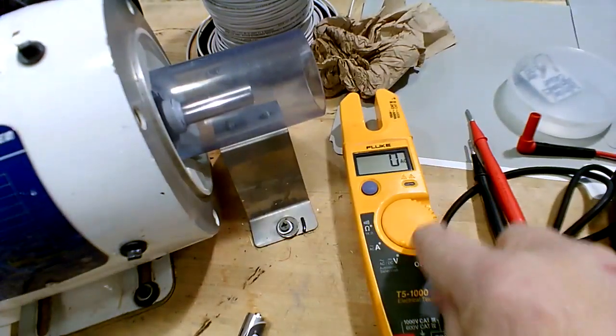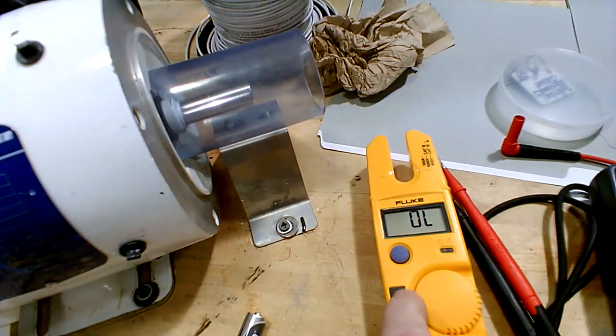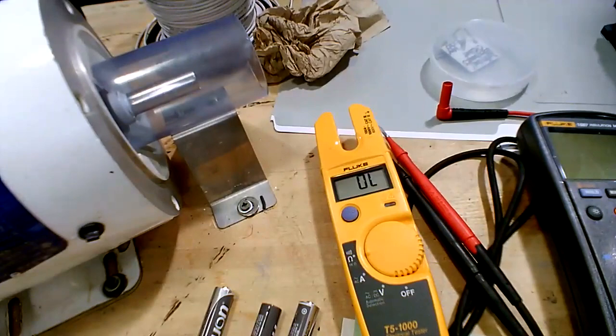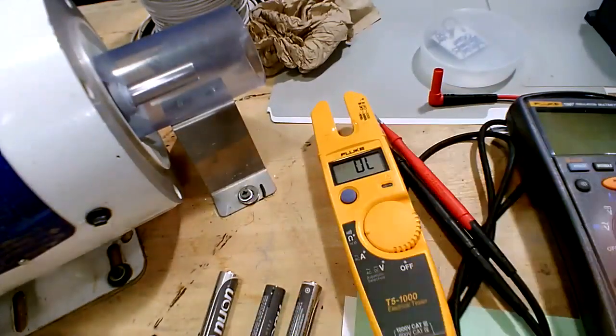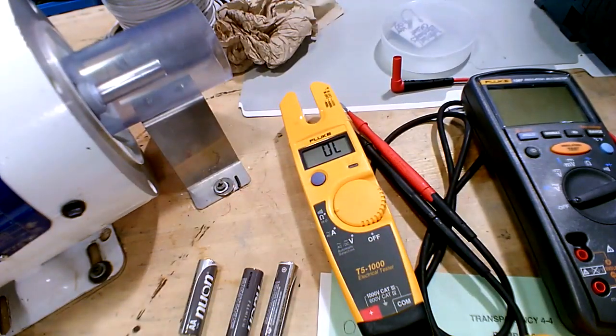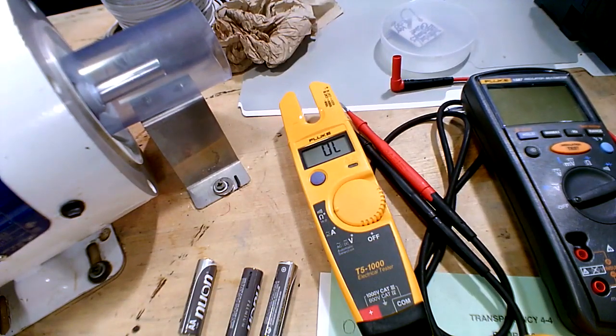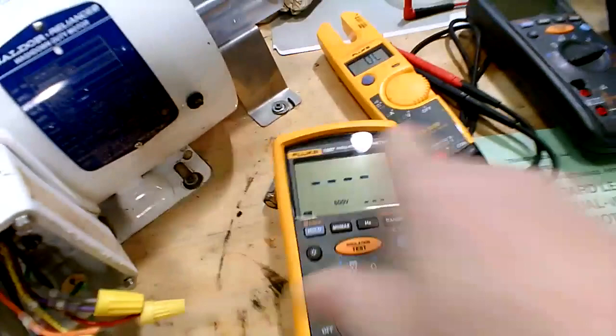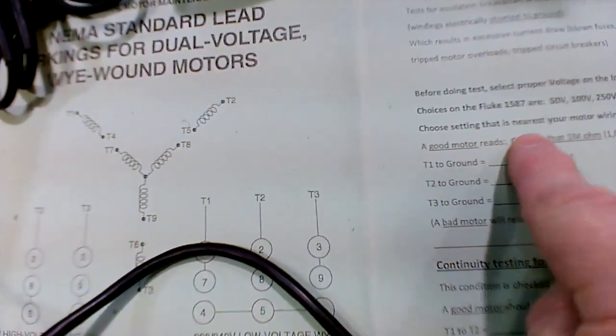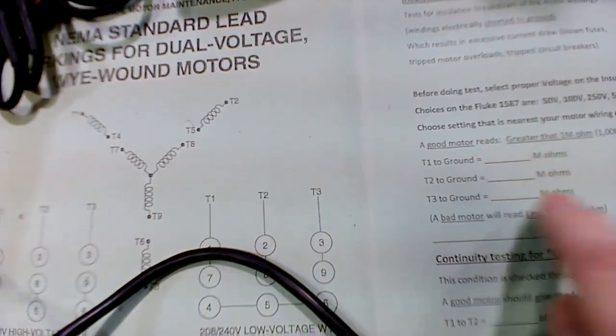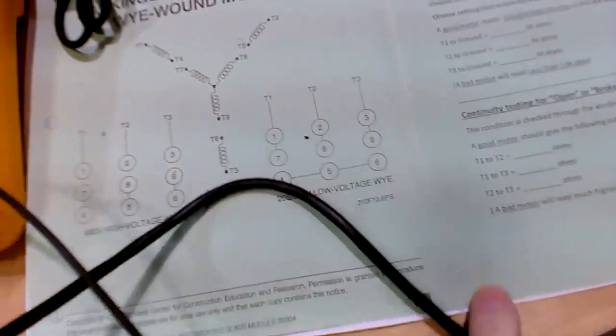Now, in some cases, a standard ohm meter checking with ohms, going from each lead to ground, a lot of times that would catch it, but not always. I've seen cases that it would not catch it, okay? So that's your first test there. And so over here on your lab sheet, you're going to put greater than 550 megohms on all 3 of these.